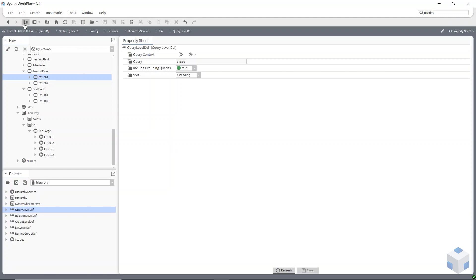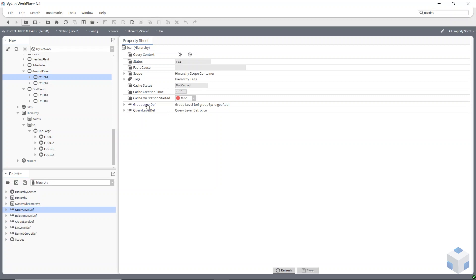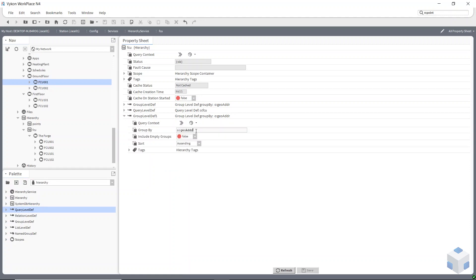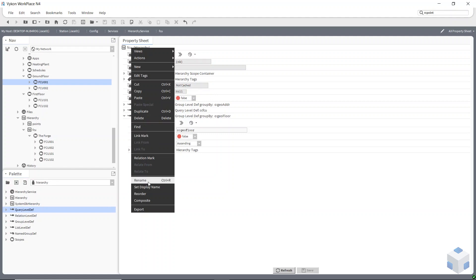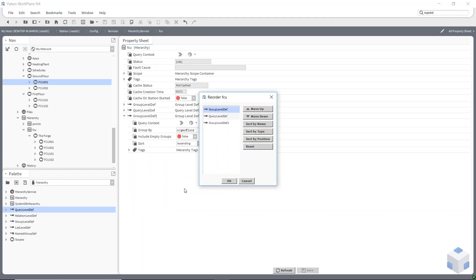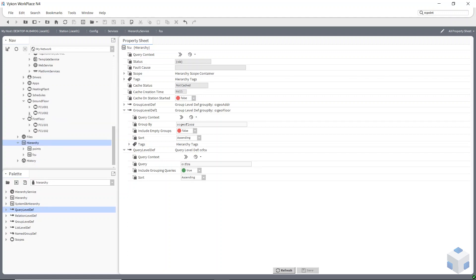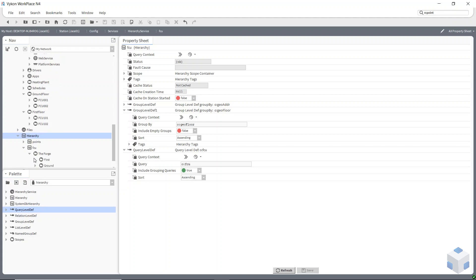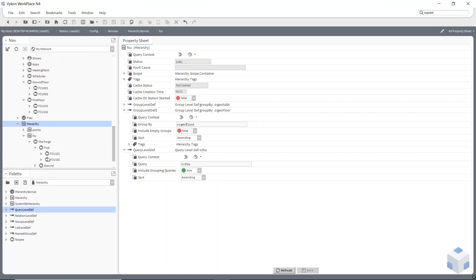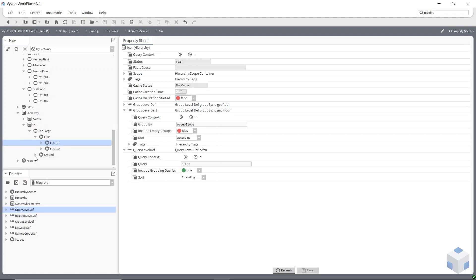Going back to my query, I'll duplicate my group level definition and change that query to geo floor. I have to reorder my hierarchy — right-click on the hierarchy, say reorder, and move the group up above the query. It always has to end in a query level definition — there is a rule to setting the order correctly. Now if I refresh the tree, I've got the Forge, then the two floors, with two fan coil units underneath the first floor and two underneath the ground floor.